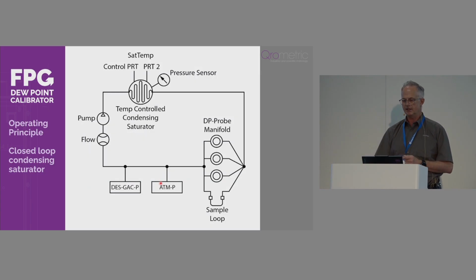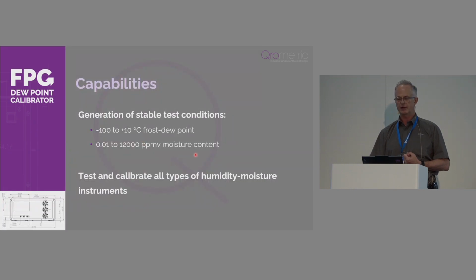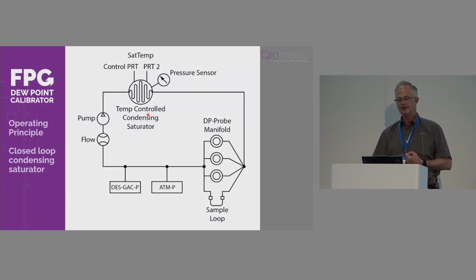How it works is, for me, many years of thinking about this, very simple. In practice, it's quite complicated because of the way that the system has to be sealed, but we have a temperature-controlled condensing saturator, which is the heart of the instrument. And we flow the gas in the system, which is sealed, in recirculation mode. So the water vapor pressure in that loop becomes equivalent to the dew point of the condensing saturator. So it's a condensing saturator. It takes the water out of the air above the dew or frost point.